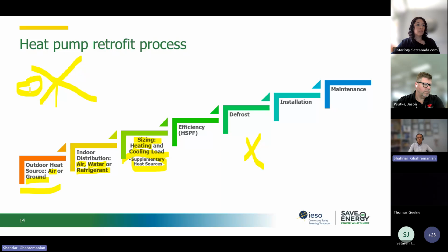So I encourage you, if you have time, just watch the recording for the residential session that we did last week for IESO, actually. In there, we have details of this sizing and supplemental heat sources. Then we go to the efficiency. I have only one of them, the heating, because it's the most important one for our facilities. We live in a cold climate, but please check the COP, please check the EER, and please check the SEER as well. So please check all four efficiency metrics of the heat pumps and decide which of them is the best.